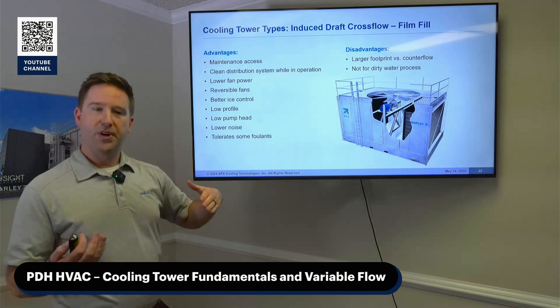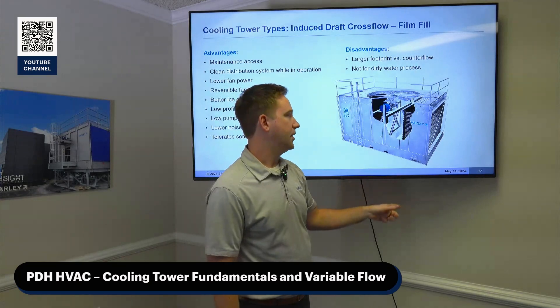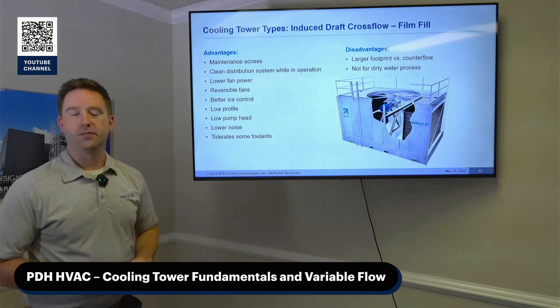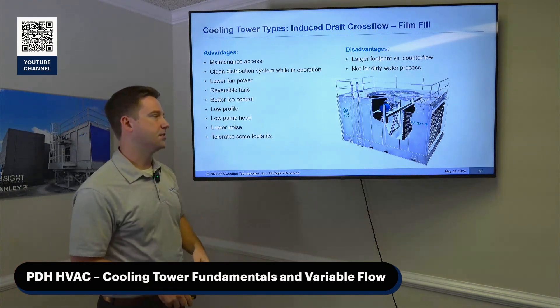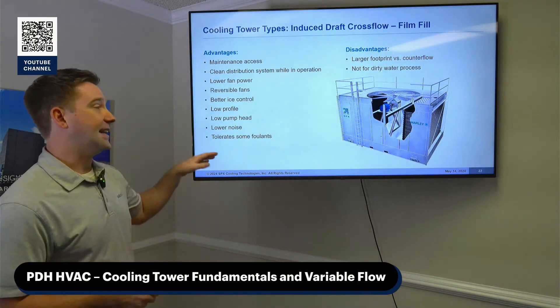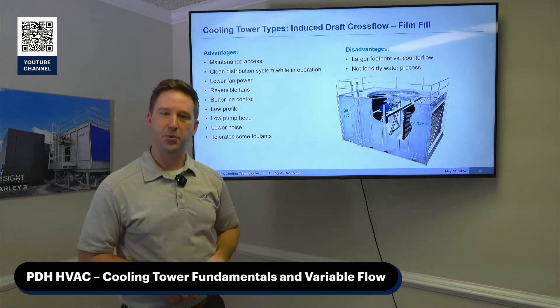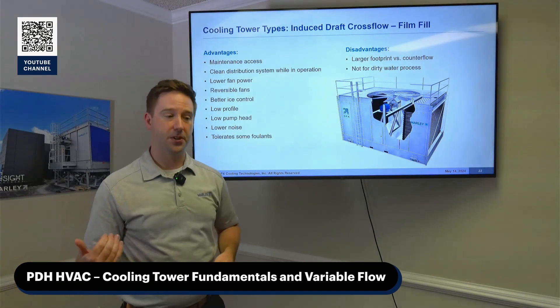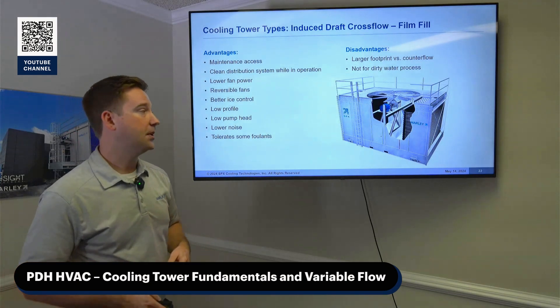Cross-flow towers also have a lower pump head than counter-flow towers, because they use a gravity flow distribution system. You pump water up into the two hot water basins, and as long as you keep four to five inches of water above those nozzles, you get the right head pressure and good water distribution over the fill. This design also allows you to reduce the flow rate down to about 33% of your design flow, which is a big benefit for variable flow applications.